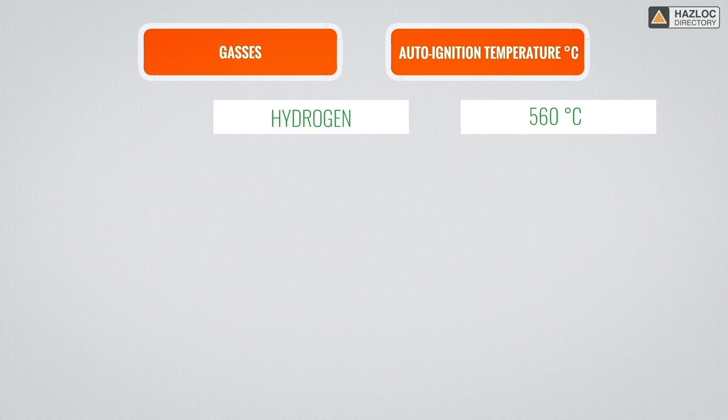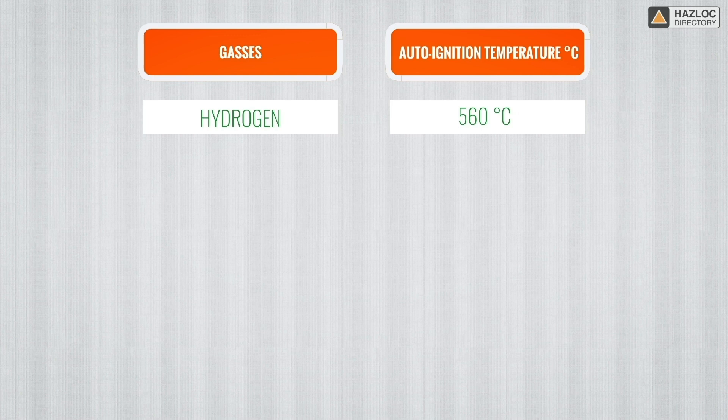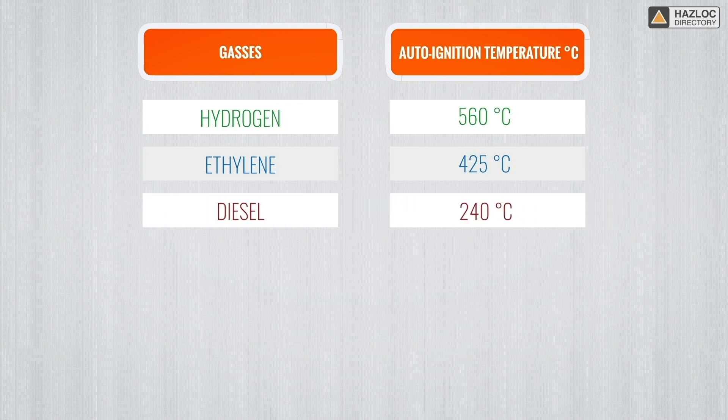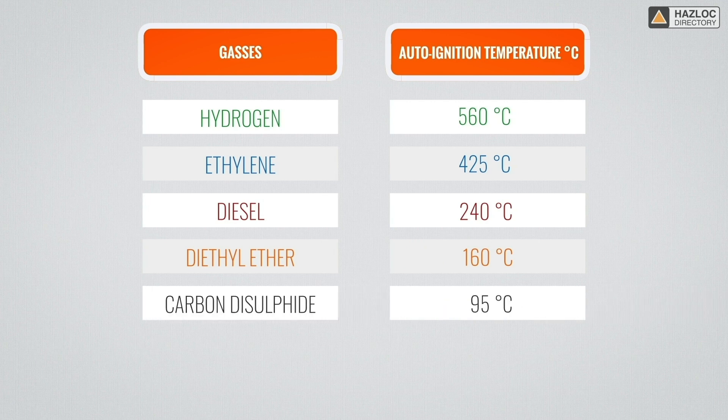For instance, hydrogen has an auto-ignition temperature of 560 degrees Celsius, ethylene 425 degrees Celsius, diesel 240 degrees Celsius, diethyl ether 160 degrees Celsius, and carbon disulfide has 95 degrees Celsius.